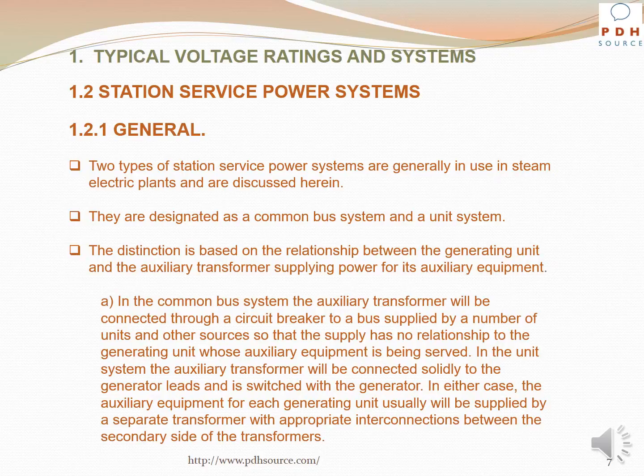The distinction is based on the relationship between the generating unit and the auxiliary transformer supplying power for its auxiliary equipment. In the common bus system, the auxiliary transformer will be connected through a circuit breaker to a bus supplied by a number of units and other sources, so that the supply has no relationship to the generating unit whose auxiliary equipment is being served. In the unit system, the auxiliary transformer will be connected solidly to the generator leads and is switched with the generator. In either case, the auxiliary equipment for each generating unit usually will be supplied by a separate transformer with appropriate interconnections between the secondary side of the transformers.